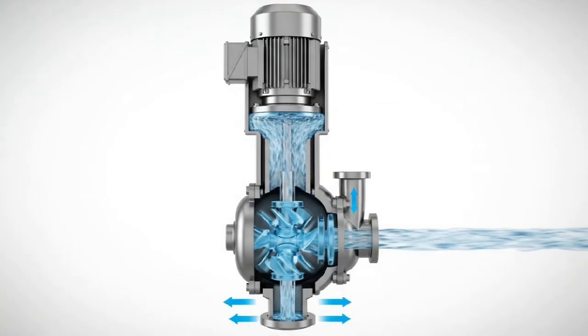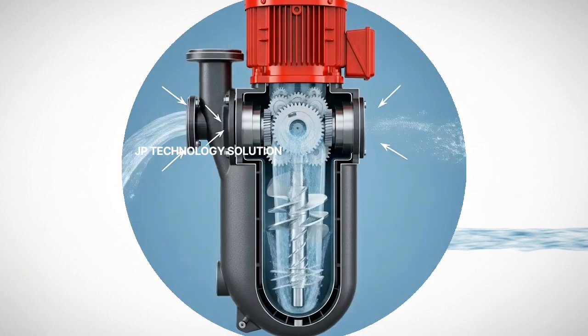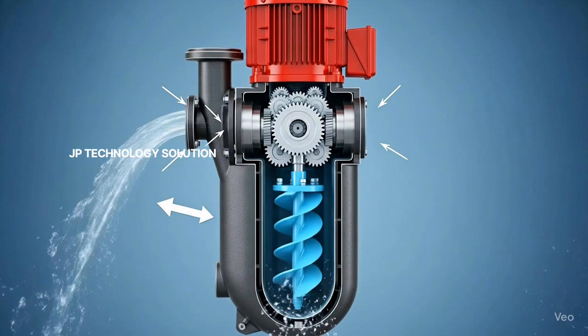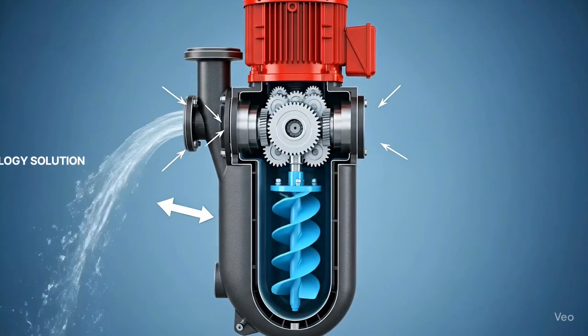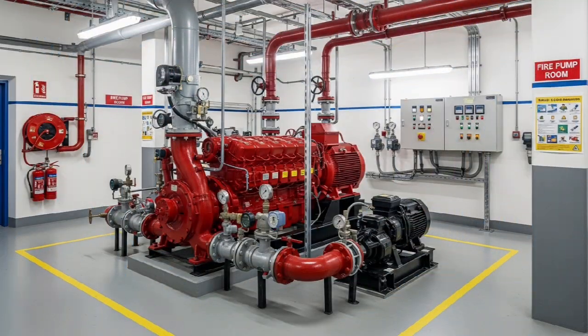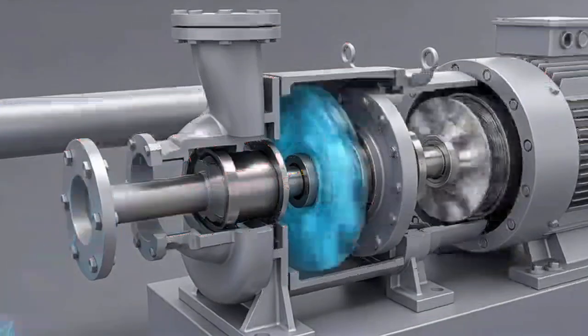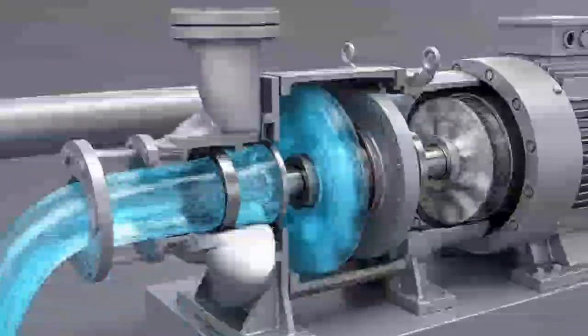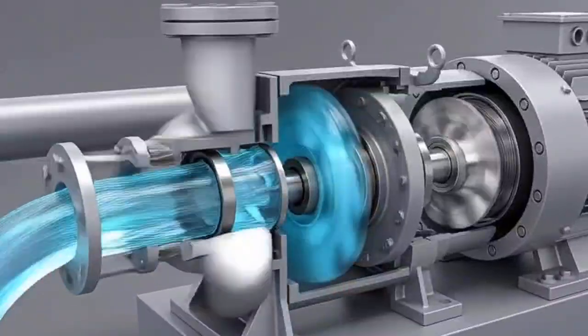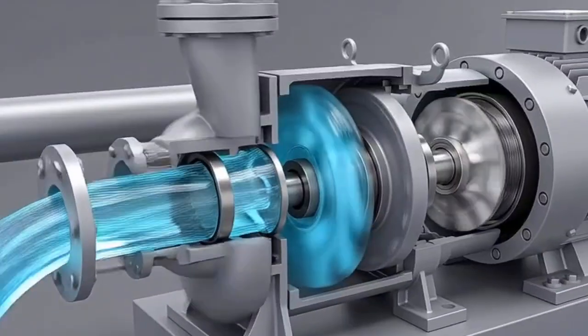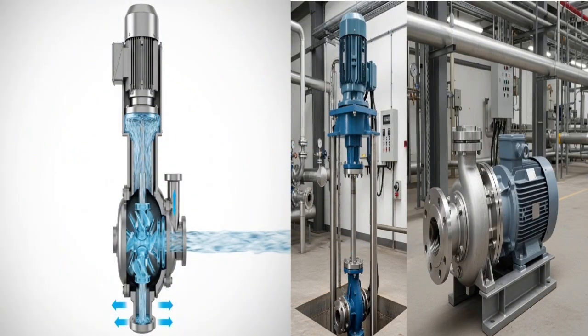In short, vertical pump advantages: saves floor space, good for underground water lifting. Disadvantages: more expensive and harder to maintain. Horizontal pump advantages: cheaper and easier to maintain. Disadvantages: takes more floor space and often requires priming.